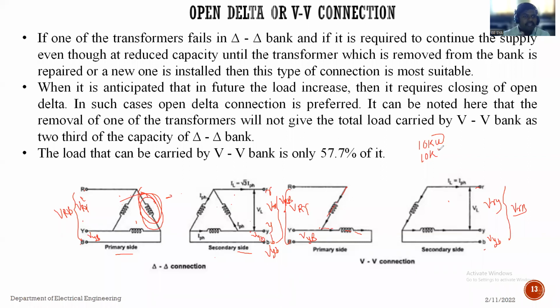If any one of the transformers fails in a delta-delta bank, and it is required to continue the supply even at reduced capacity - if the load was 100 kVA, the transformers will not be able to carry that full 100 kVA. They will be able to carry about 57.7%, or near 60%, or above 50% load.